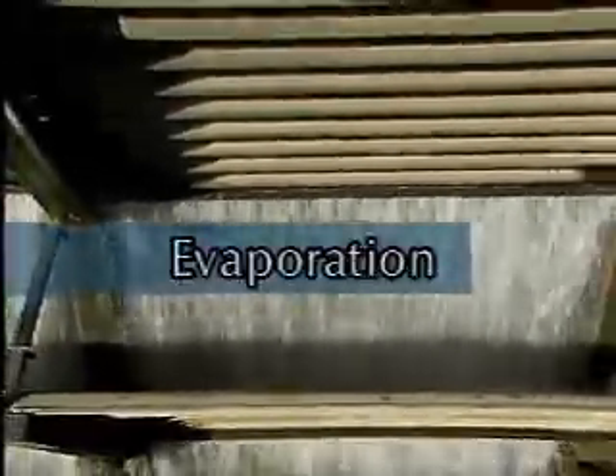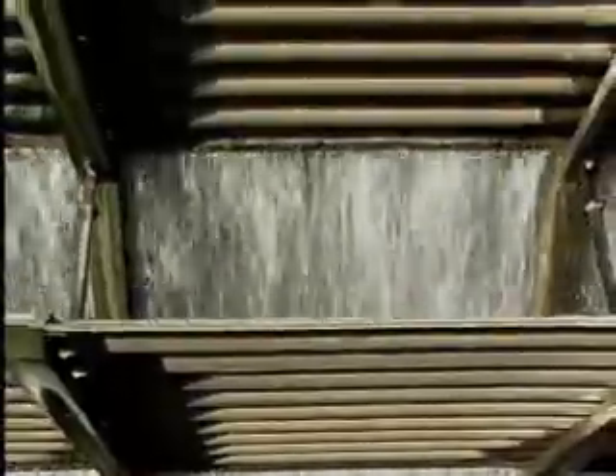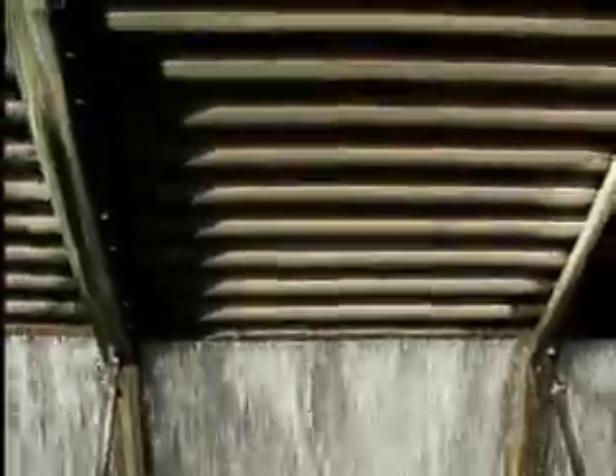Evaporation is a process in which the heat in the water causes part of the water to turn into vapor. As the water is turned into vapor, the heat is removed. As a result, the remaining water is cooled. In a cooling tower, heat that was in the water leaves the tower in the vapor as the water evaporates.